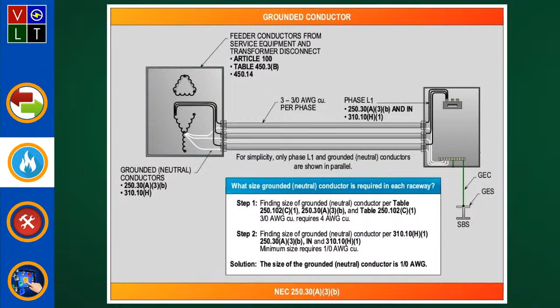1/0. Yeah. Okay. So if I'm looking at this illustration and sizing the grounded neutral conductor that's required in each one of those raceways, I'm going to be looking at Table 250.102(C)(1). And if I pick up 3/0 conductors, it's going to tell you it's required to be a number 4. But if I go over and look at 310.10(H)(1), it tells you the minimum size has to be at least what? A 1/0. Yep. Because that's where I pick up all my information for parallel conductors.